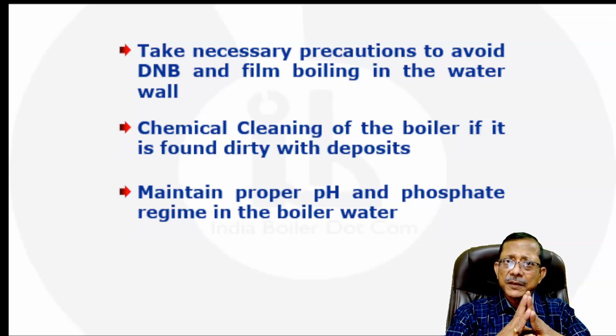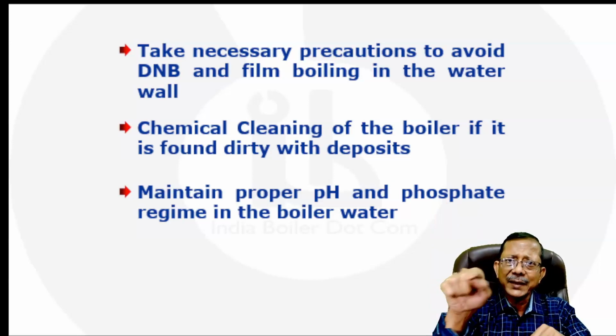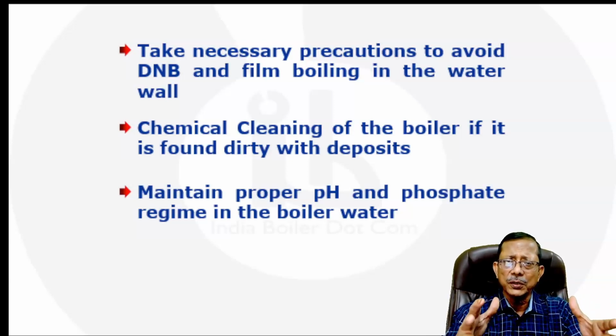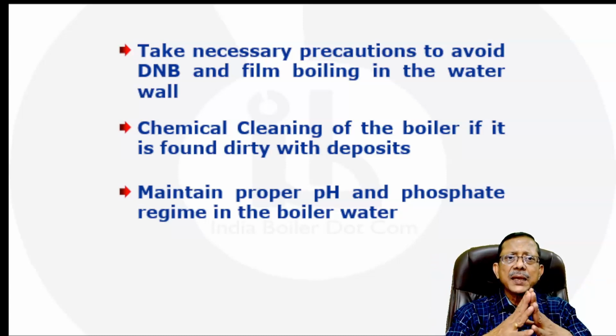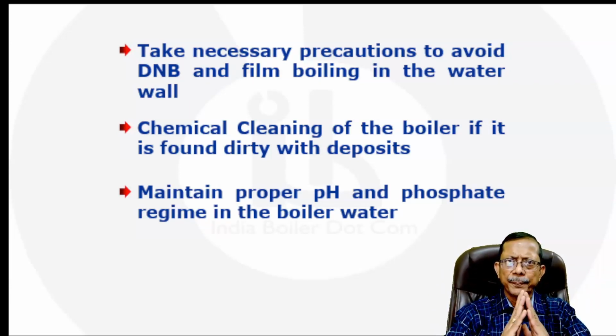That is very damaging. First of all, we need to understand why the phosphate is going with the steam and stop that particular reason, right? Not reducing the phosphate, which is basically required in the boiler water to take care of this corrosion. If I get some chance, I might also create a video on the caustic corrosion itself, right? How to control the caustic corrosion, what causes the caustic corrosion. But for the time being, let us say the pH and phosphate has to be maintained properly, right?